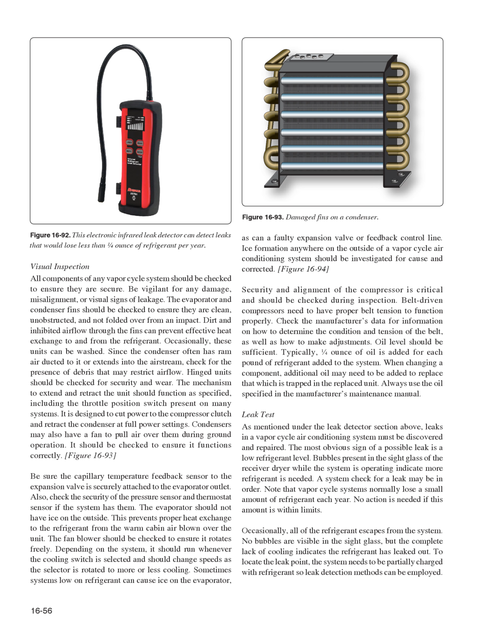Figure 16-93, be sure the capillary temperature feedback sensor to the expansion valve is securely attached to the evaporator outlet. Also, check the security of the pressure sensor and thermostat sensor if the system has them. The evaporator should not have ice on the outside. This prevents proper heat exchange to the refrigerant from the warm cabin air blown over the unit. The fan blower should be checked to ensure it rotates freely. Depending on the system, it should run whenever the cooling switch is selected and should change speeds as the selector is rotated to more or less cooling.